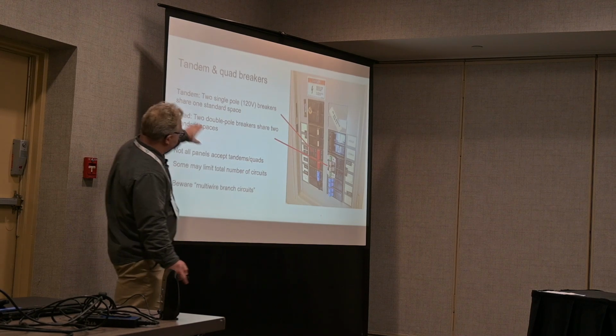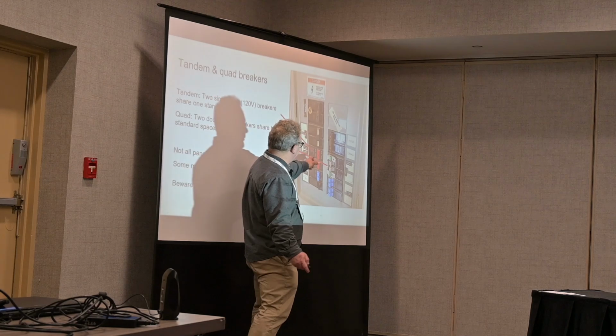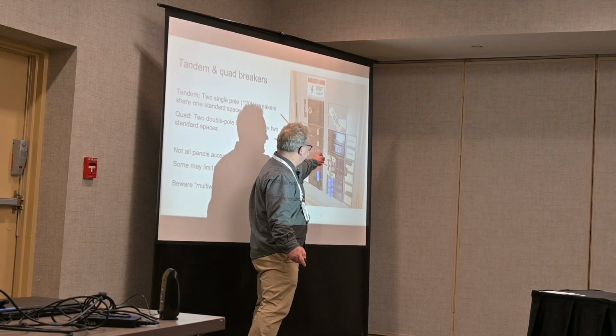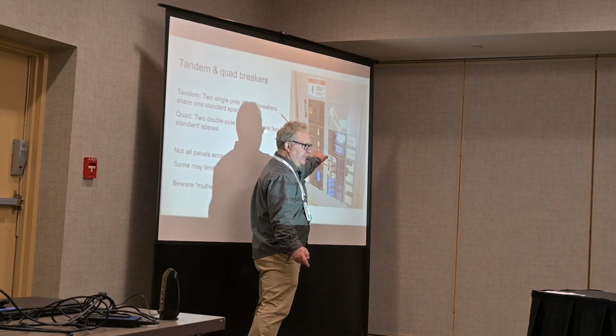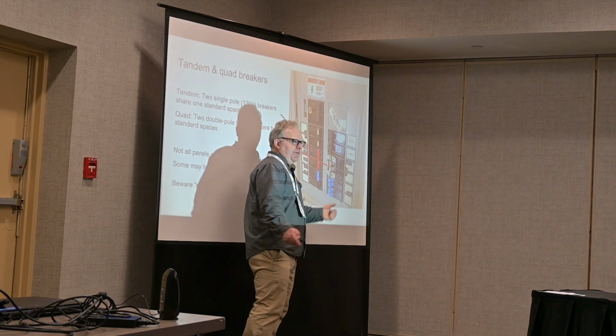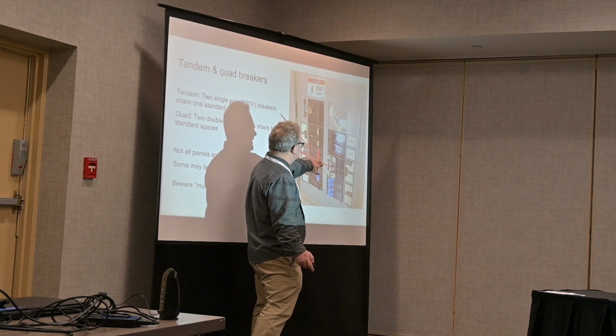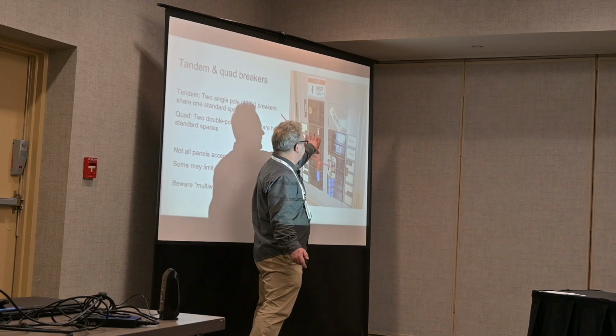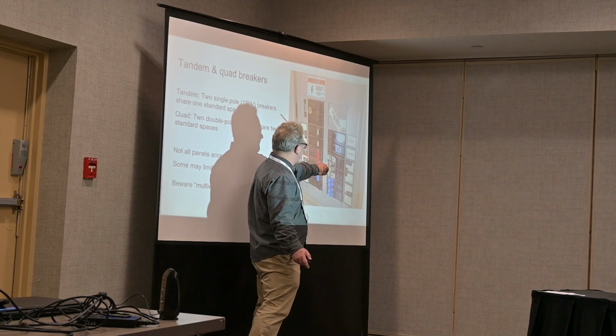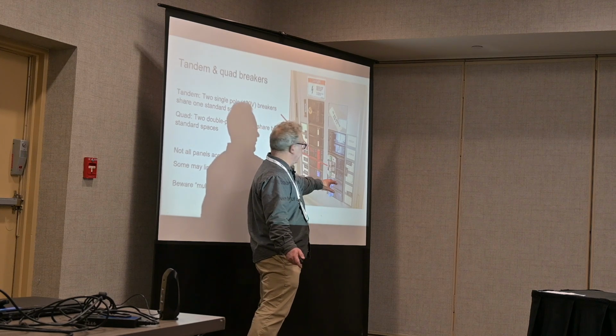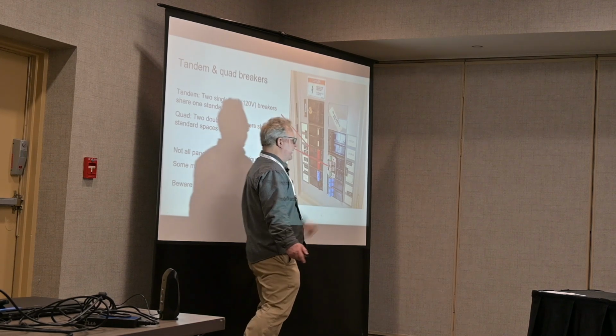So tandem breakers are like what we see here. In a standard sized space, we now have 2 single pole breakers. This is a very common strategy. To free up one space, you need to install a tandem breaker. To get enough for a double pole circuit, you're going to need 2 tandem breakers.